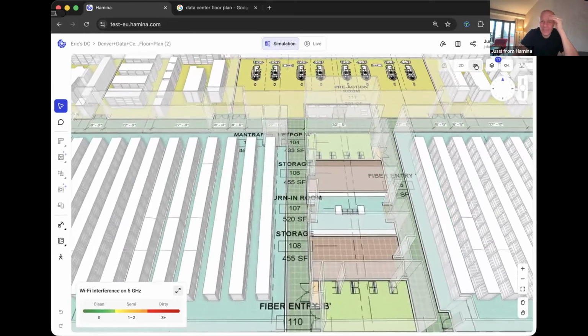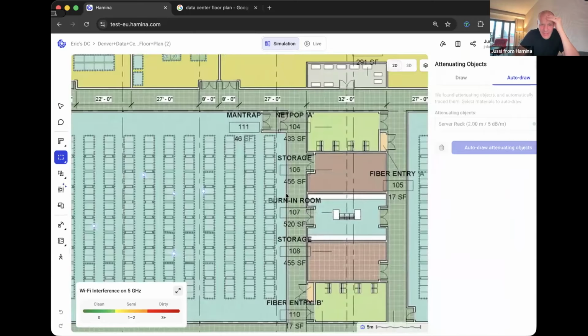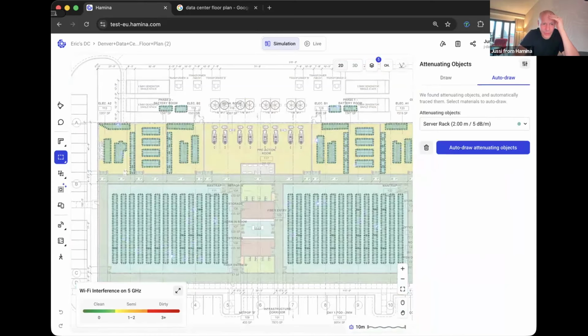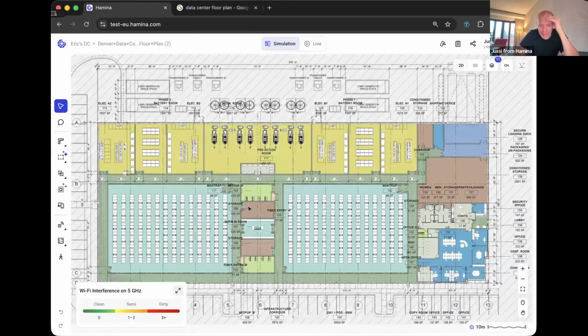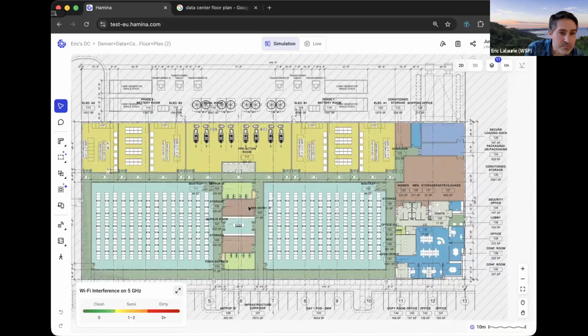So is this floor plan something you would typically see? Yeah, that's pretty typical. It varies between clients - the way they arrange the building around the data halls, the way they arrange the racks, and the way they arrange the cable baskets for the telecom optical fiber will change. But overall, it looks like this more or less.